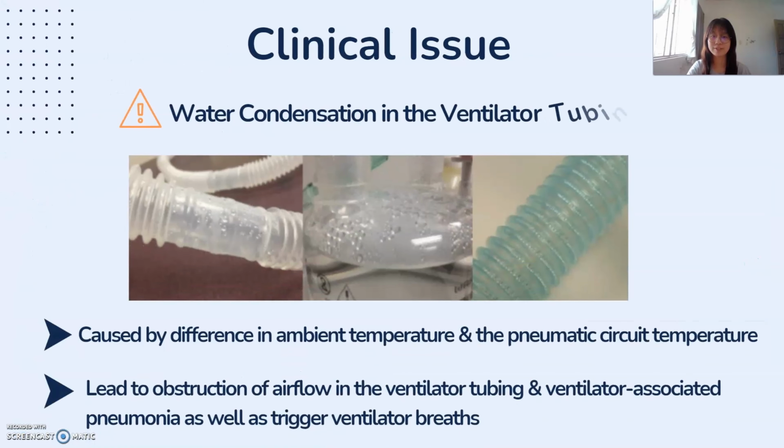Next, we proceed to the clinical issue. Water condensation in the ventilator tubing is one of the clinical issues that has been discovered during our visit to the NICU of the Department of Pediatrics in UMMC. Water condensation in the ventilator tubing is caused by the difference in ambient temperature and the pneumatic circuit temperature.